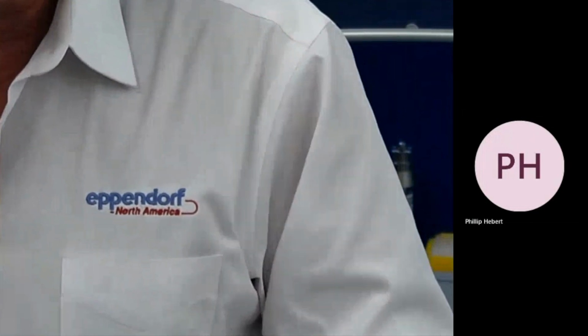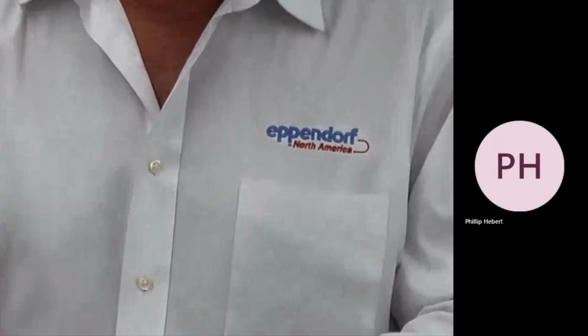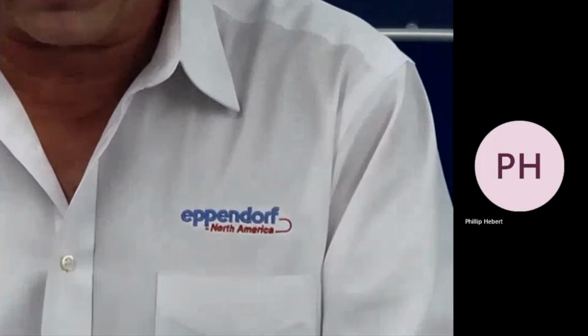Where did you get these from? And they said, well, we got the Thermo tips, the epMotion tips. They had advertised them as epMotion tips, and so I said, interesting, let's try it with our tips. It had crashed using an alternative tip, simply because the tips didn't attach in the proper way. So we don't recommend that you use those other tips. There are some people who use them and get passable results, but for a very precise application like this, I would say it's better to stick with something that we know is not going to damage the machine.